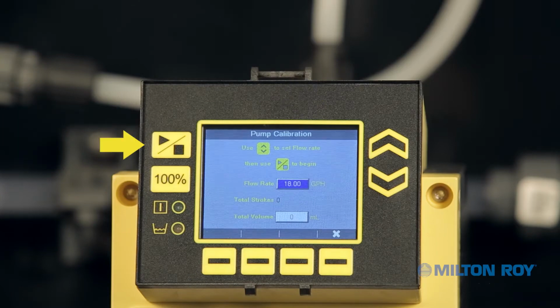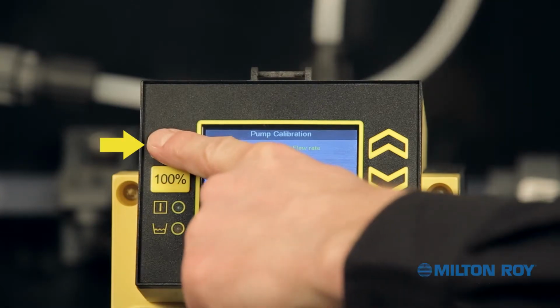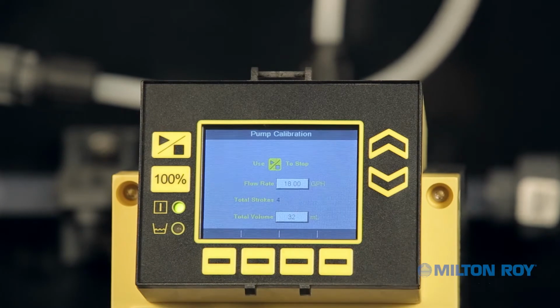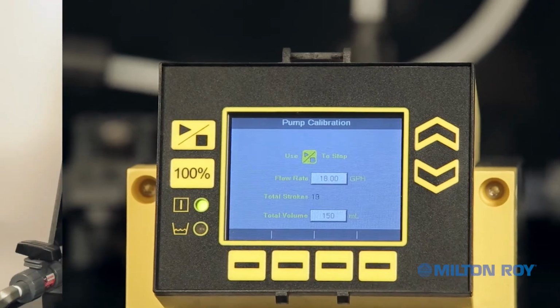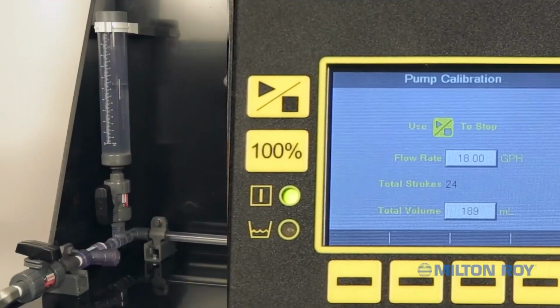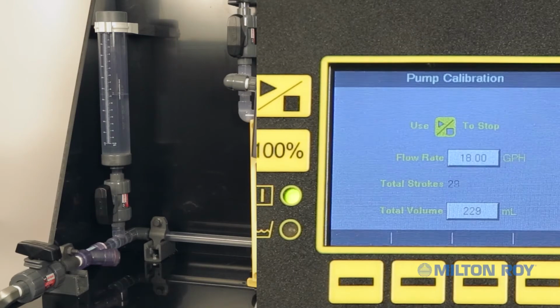Press the Start/Stop button on the left side of the display to start the pump. The green LED power light will illuminate to show the pump is now operating. While the pump is pumping, the stroke count and total volume on your display will increase, and fluid will begin to empty from the calibration cylinder.